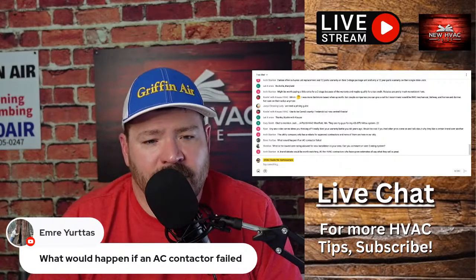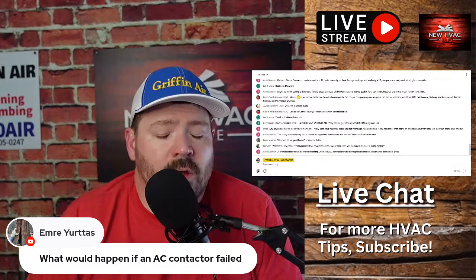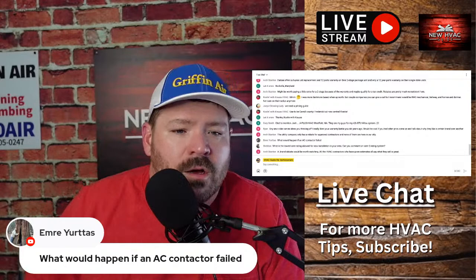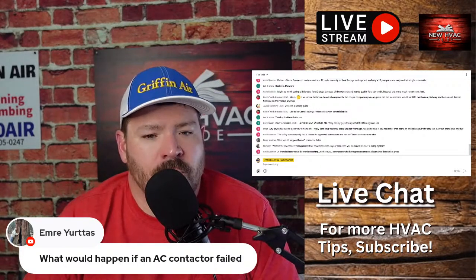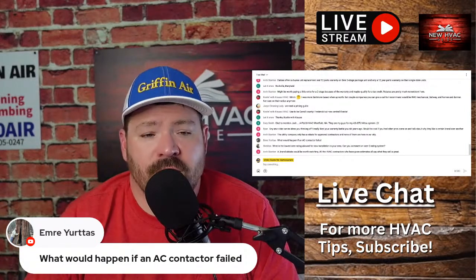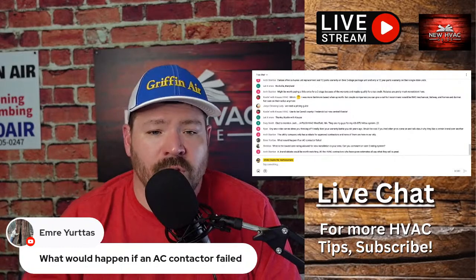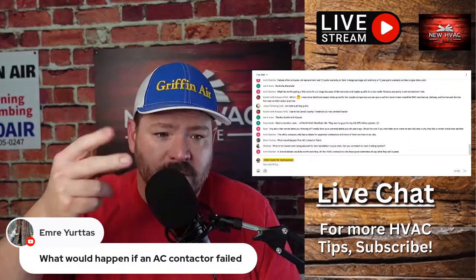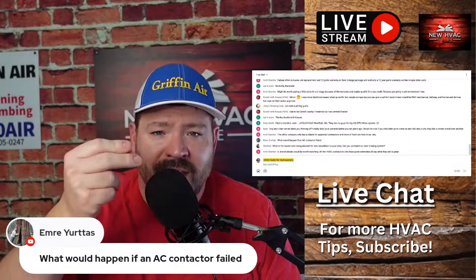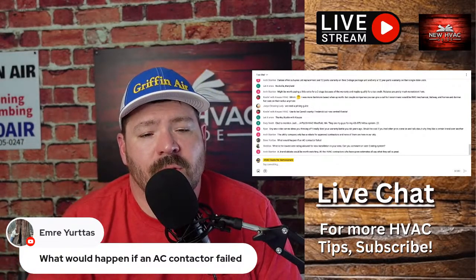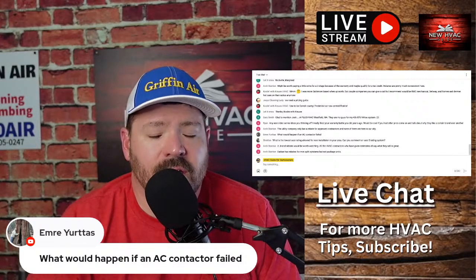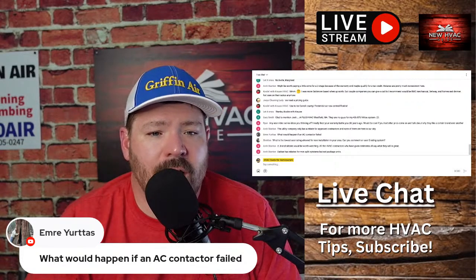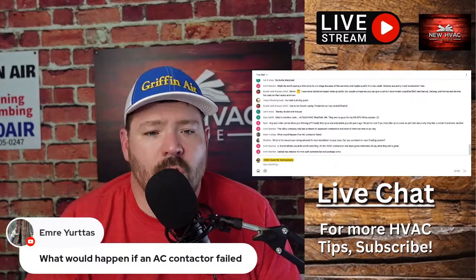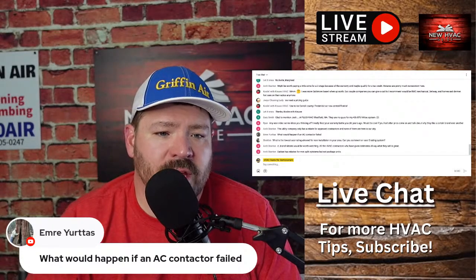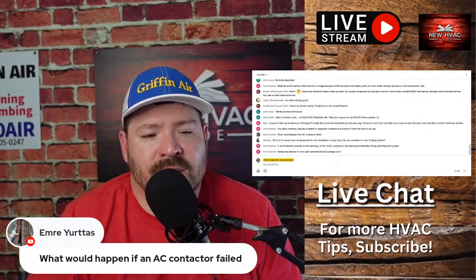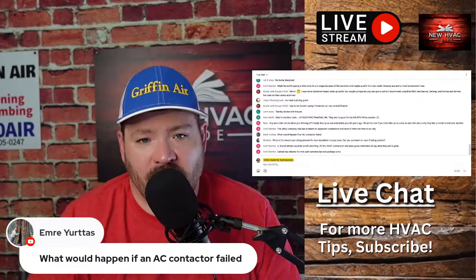Emre asks, what would happen if an AC contactor failed? Well, they fail from time to time, and different things can make them fail. Contactors are one of the electrical components still used today, and have been used for the last 50 years. They're very simple, literally just a solenoid that pulls this little flipper, this little plate, down, and they fail from time to time. What would happen is they simply wouldn't operate, especially if that solenoid had some sort of issue—maybe the resistance is too high, or an open winding, or whatever reason it's no longer pulling in like it should. Usually they just have to be replaced. They're a pretty insignificant part, meaning less costly than, say, a compressor or a board.